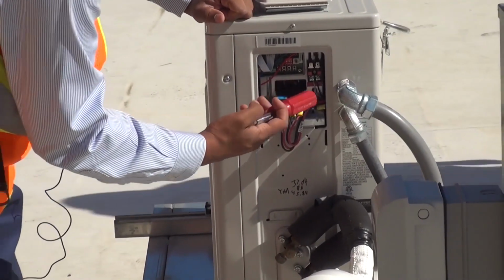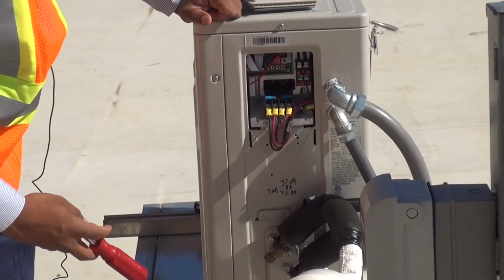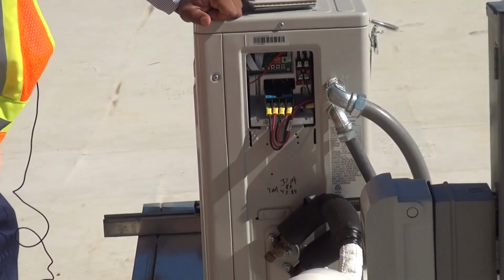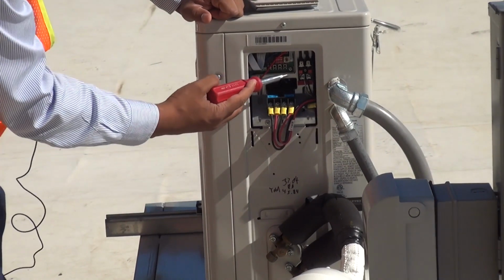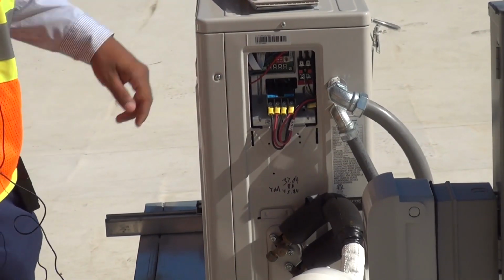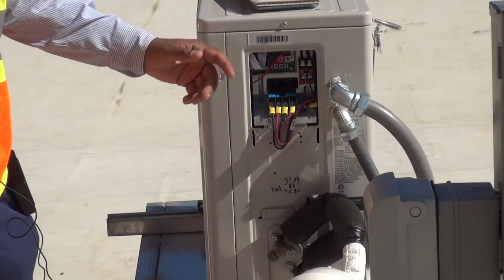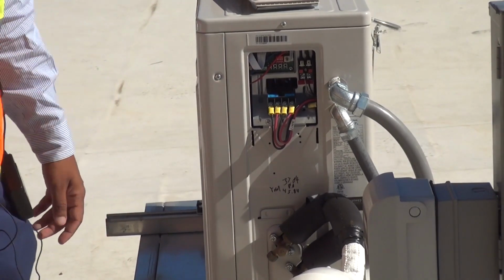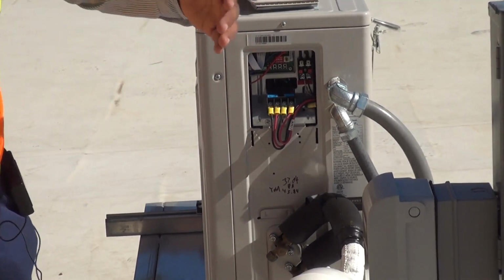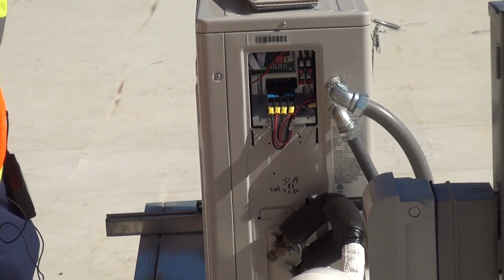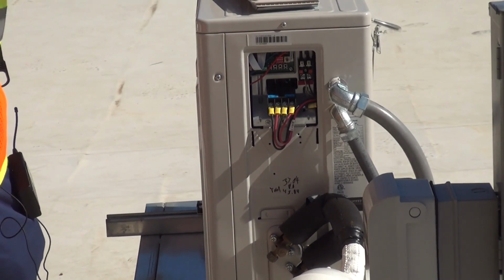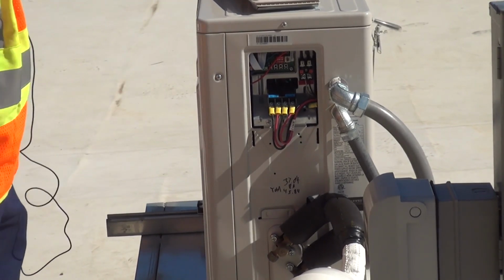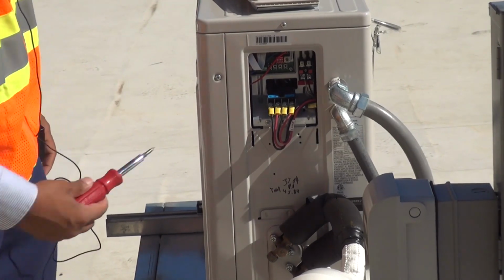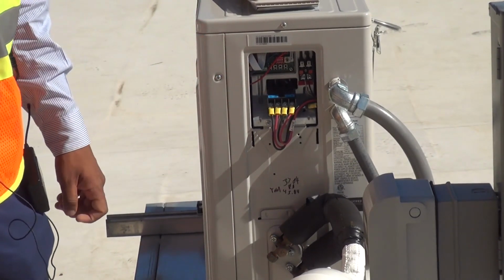On the inside here, this is where your line voltage will be coming in from your disconnect. We have our F1, F2 terminal bus, and that F1, F2 is your internal communication. It's a set of wires that go from your indoor to your outdoor that gives it communication on how to modulate. As the outdoor unit ramps down, it gives that signal to the indoor unit, so they're both in unison. If you ever do get the service tool and connect to it, the F1, F2 is where you connect to it.